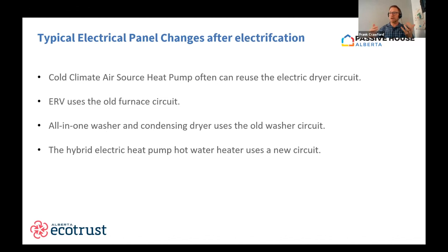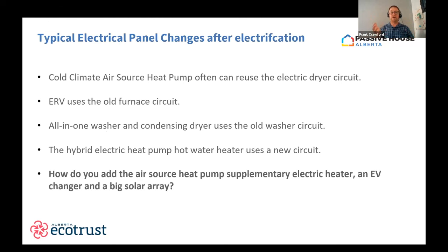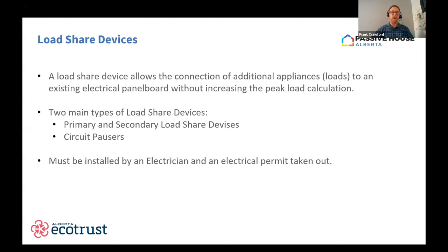So not many changes, but you're probably asking, how do I add that air source heat pump supplementary electric resistance heat? I want an EV charger and I want a big solar array. So how do we add those? The answer is we use what is called a load share device. A load share device is any electrical device that allows the connection of additional appliances or loads to an existing electrical panel board, but doesn't increase the peak load calculation for that panel board.